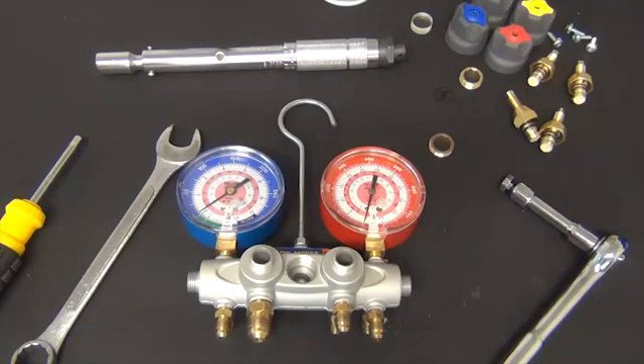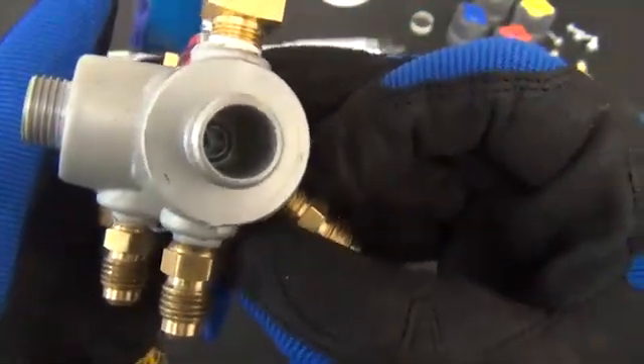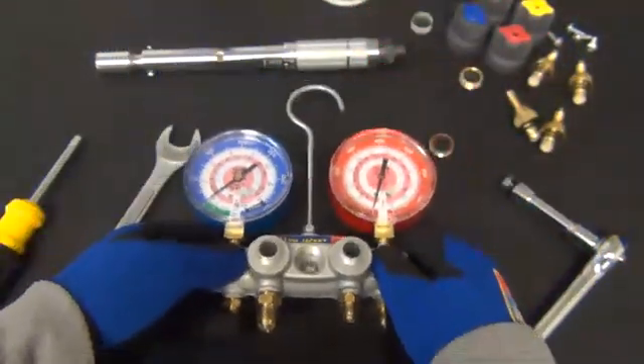After you have cleaned the manifold bore, you will need to inspect each bore and seat for any deep scratches, dents or pitting. If any are found, the bore should be replaced.